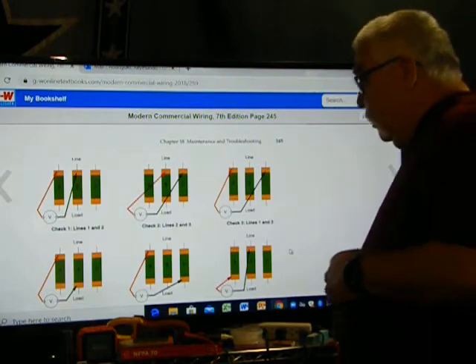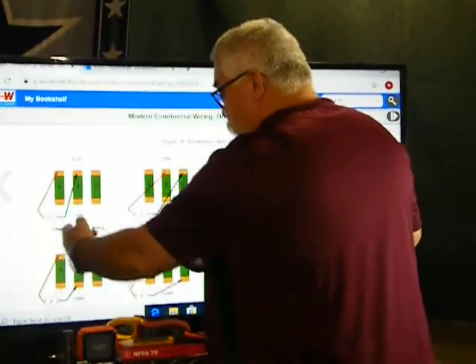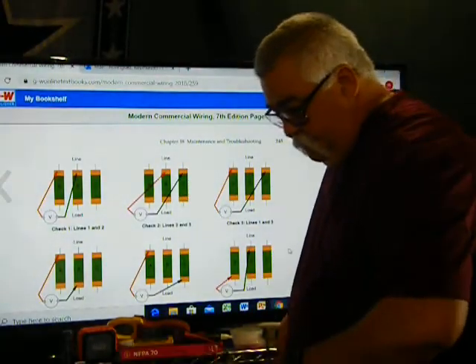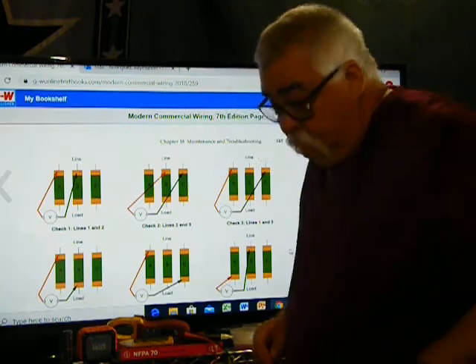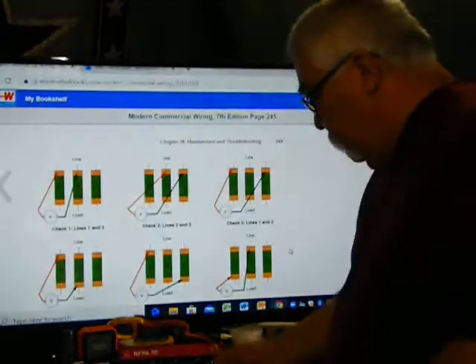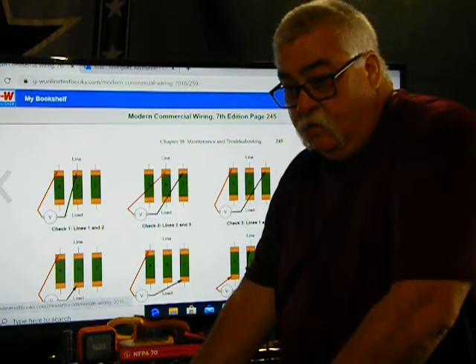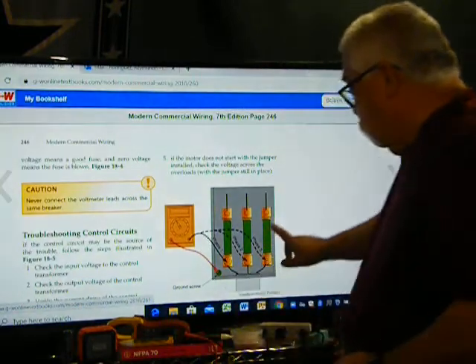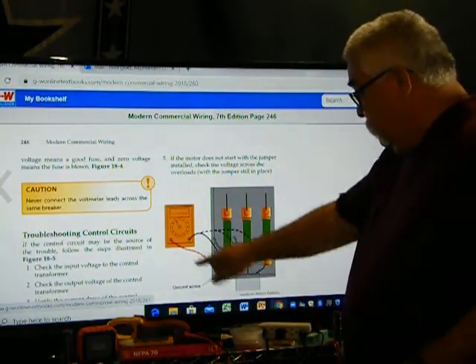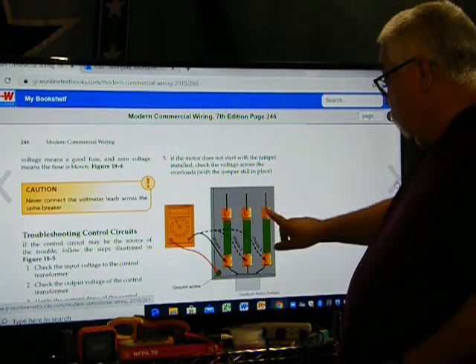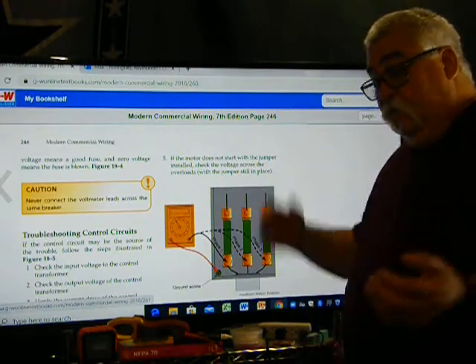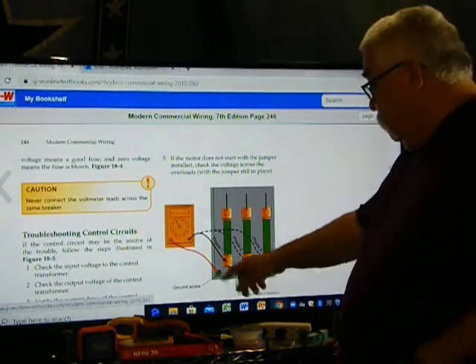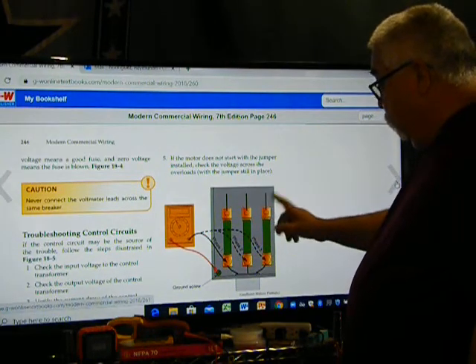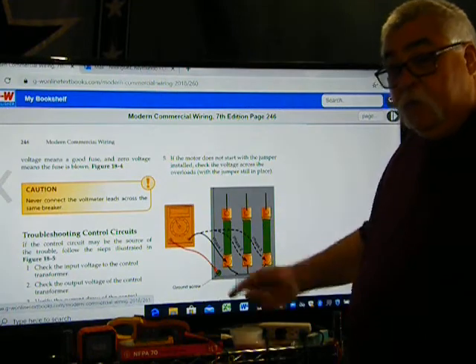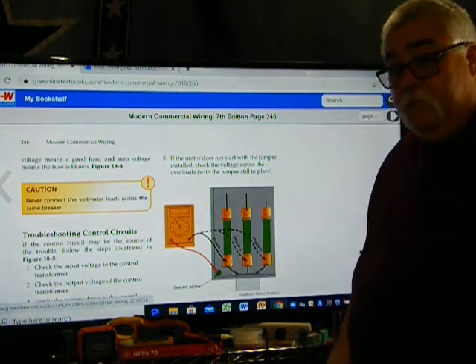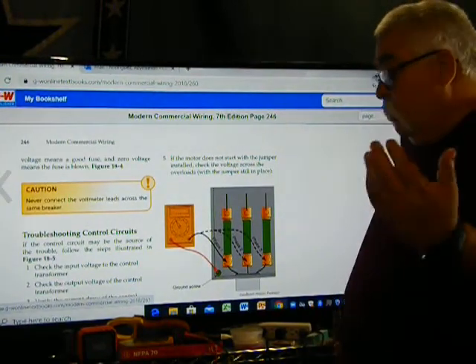Yesterday I said that I would go from a ground, so the metal frame, go back here, oops, got the mouse over here. This is your textbook, so I have this one here. So the other thing I can do is I can find the ground screw, go to hot, hot, hot. So if I establish these are all hot, let's say I got a 240 480. So I'll go from here to here, I got 240, I go to here, I got 240, I go to here, I got 240. Guess what? When I come down here to the bottom, I should get the same thing. If I don't, then one of those fuses may be bad. Okay? Or it's a 120 240 or 120 208.